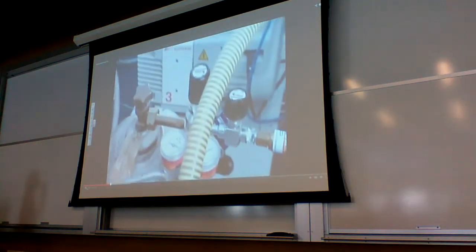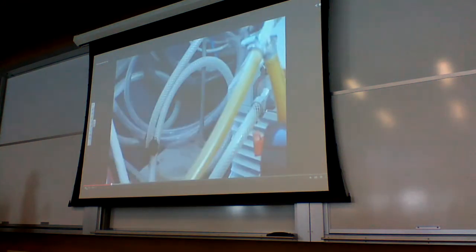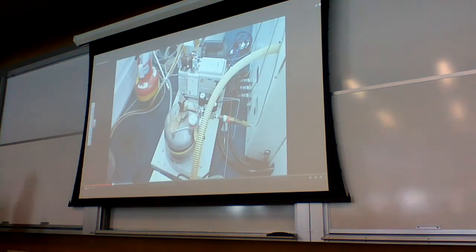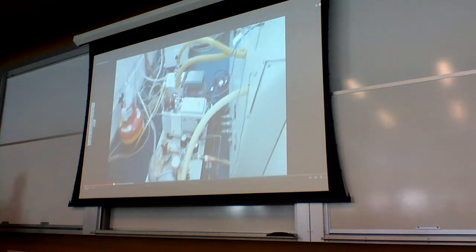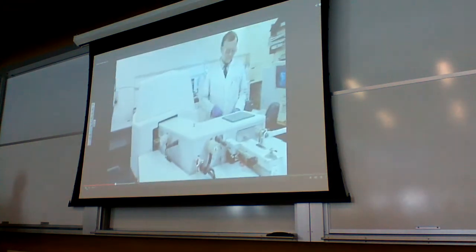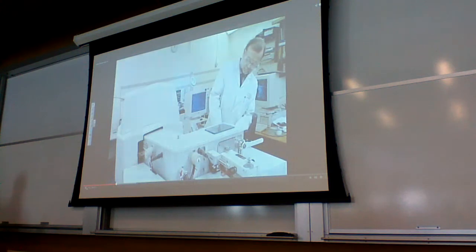These pumps keep the interior of the instrument under a high vacuum. This is to allow the ions, which are moving at speeds of many kilometers per second, a free path without collisions with air molecules. As the ions are formed from molecules of the sample, they may fall apart or fragment. The ion of largest mass is here.